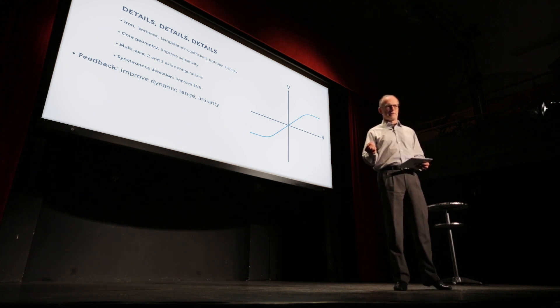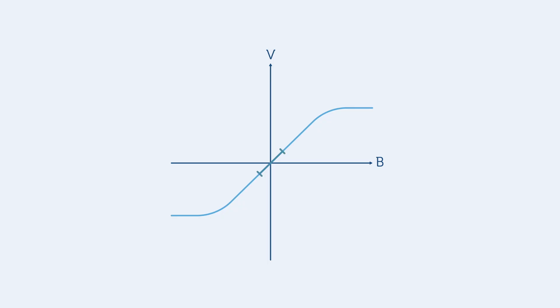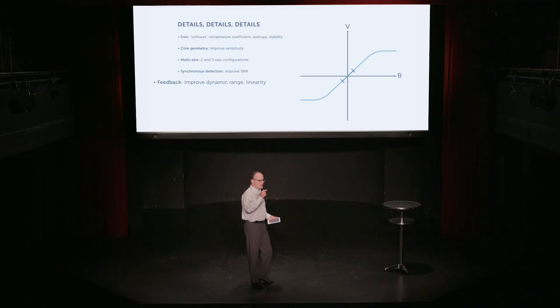Now, one way of addressing that is to use the flux gate sensor in a feedback loop that drives a current that offsets the actual field, the external field. So the sensor is always measuring something around zero, exactly in its linear region, and the actual measurement is what the current source is driving to offset the external field.